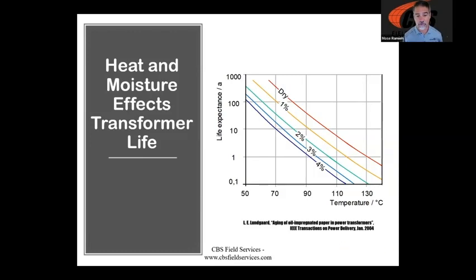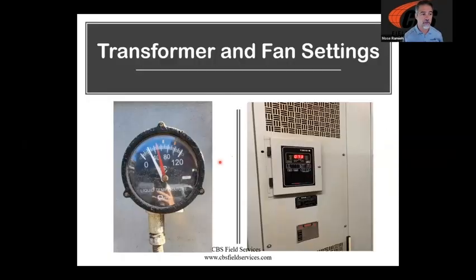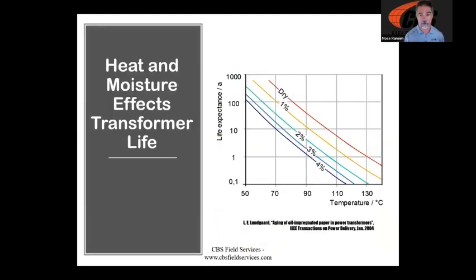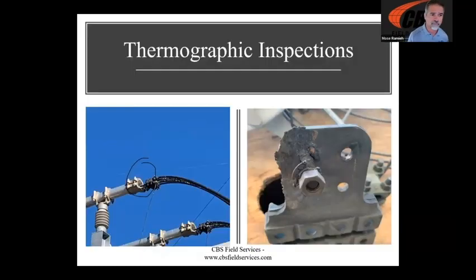So I always like to encourage our clients to lower these down to something reasonable. I mean 40, 50, 60 degrees C, something in there. I oftentimes see the dry type transformers set at as much as 110. That is the rating of the insulation. But once again, if we can run our transformers cooler, by and large, they're going to last longer. And we've already hit that slide.